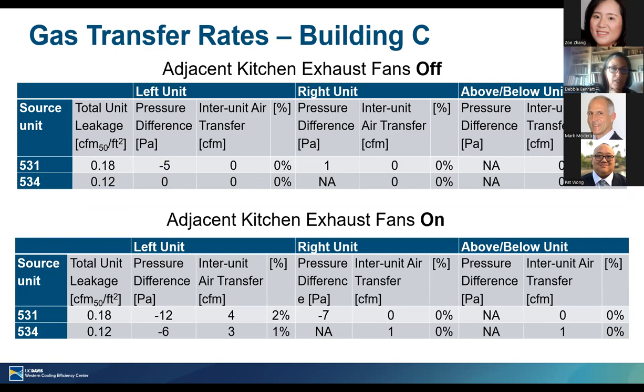Here is the same information for building C. We selected two units with different leakage levels based on natural variability in the building. There was virtually no transfer when the kitchen fans in the receiving units were off — essentially all zeros. When we drove a pressure difference by turning the receiving unit kitchen fans on, we saw about 1–2% coming in, particularly when crossing over bathroom walls.